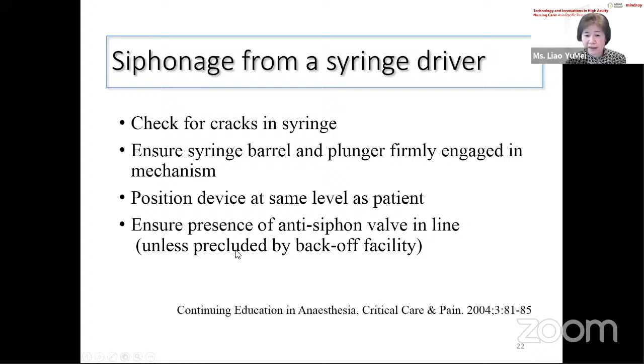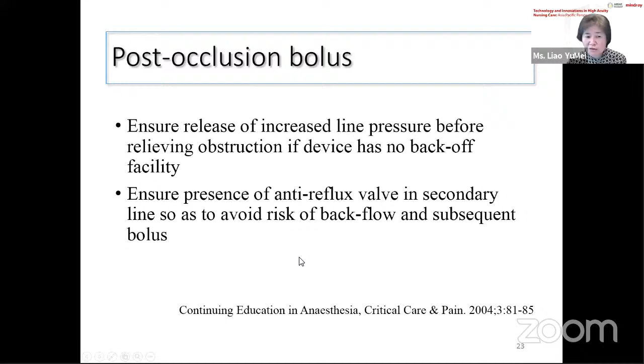Post-occlusion bolus: ensure release of the line pressure before releasing the obstruction. If the device has no back-off facility, ensure an anti-reflux valve is present in the second line, so as to avoid the risk of backflow and subsequent bolus.